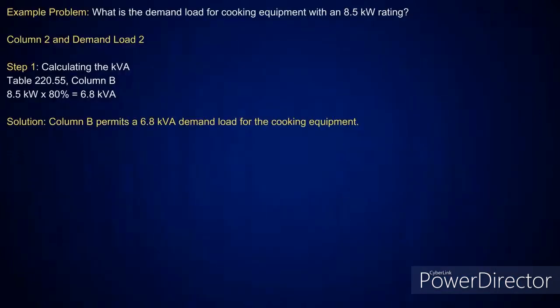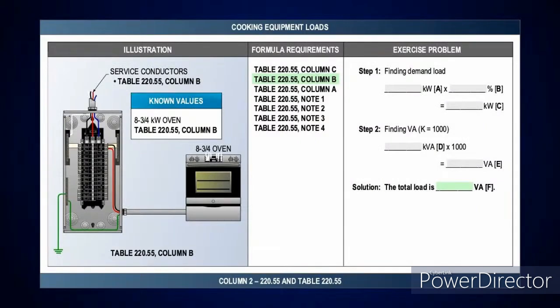Now here's one at 8.5. It's in the range of 3.5 to 8.75, and 8.5 is below it. I've got one unit, come down, pick up my number of appliances in the left-hand column, one, come across, and it tells you take it at 80%. So I'll take the 8.5 kW at 80%, which is 6.8 kVA or 6,800 VA. Very simple. And then here I've got an 8.75 that still falls within that range. I come across one unit, you're going to take it at 80%, and there's your kW rate. Then take it at 1,000, and that gives you your VA.